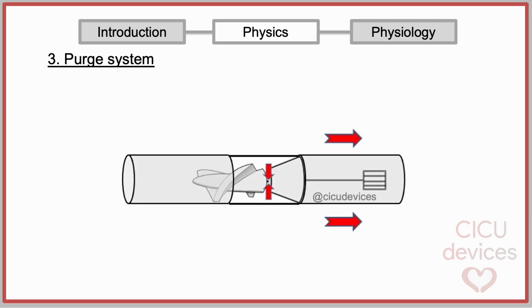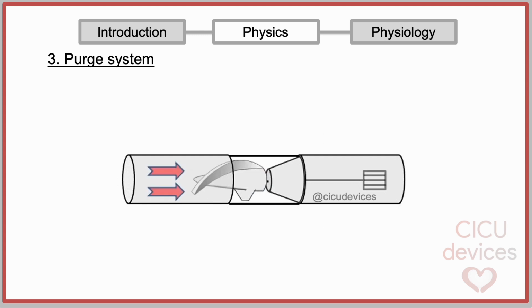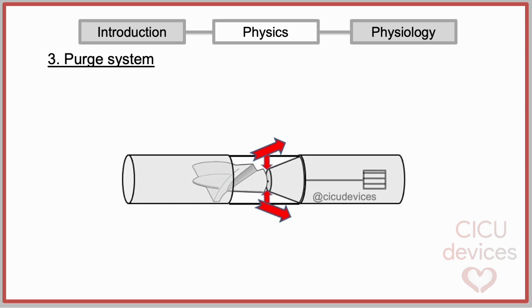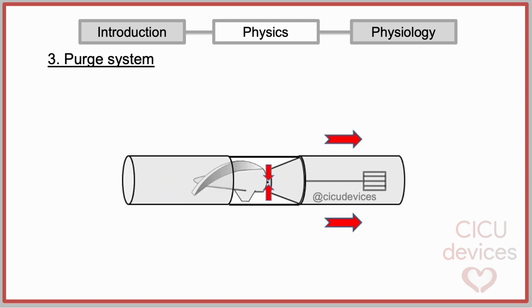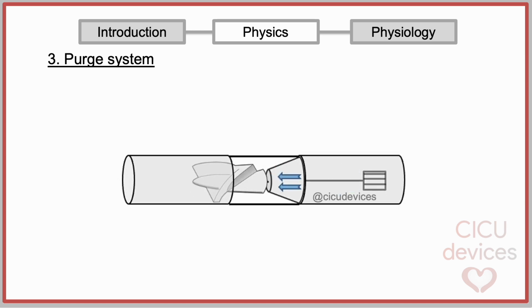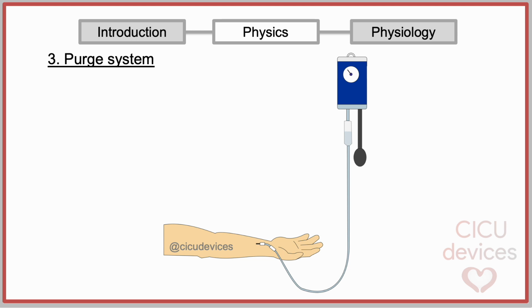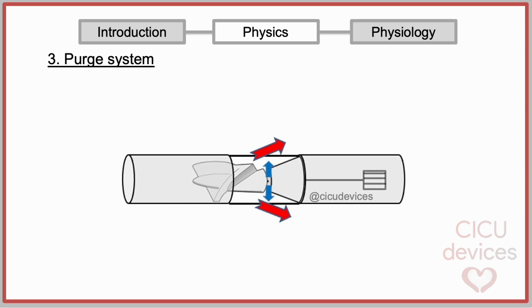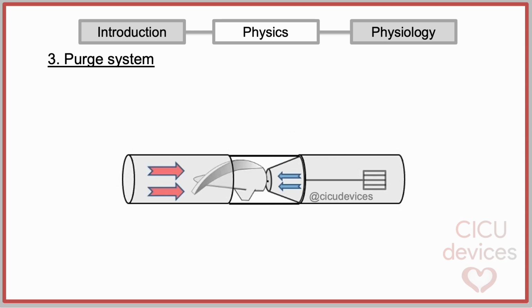The axial pump mechanism of the Impella is not completely isolated from the bloodstream. This would result in some blood flow entering the system. If the blood comes into contact with the mechanism or the engine, it begins to form a clot that would progress to impede the functioning of the system. So, the device's design incorporates a purging system consisting of a constant flow of liquid at a preset pressure. The physics of this matter is the same that compels us to place a pressurized intravenous solution in an arterial line to prevent blood backflow. In this way, the perfused purge flow at a pressure above the blood pressure at the aortic root prevents the entry of blood into the mechanism and the formation of clots.